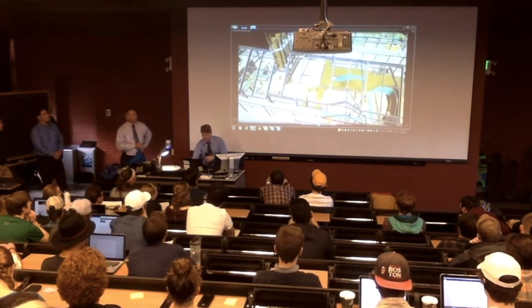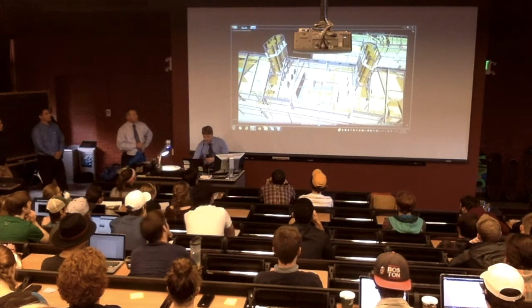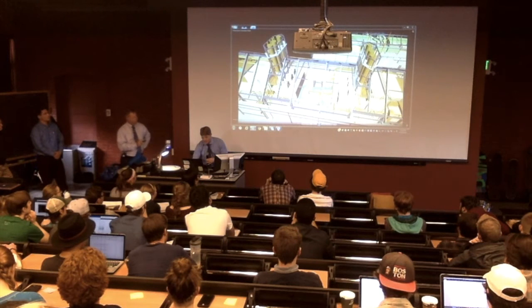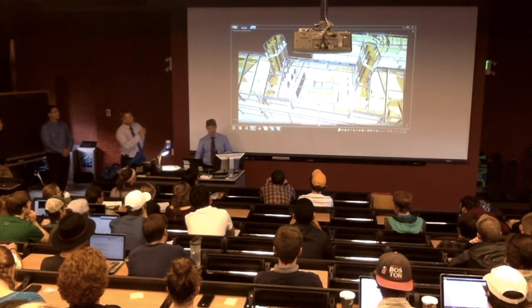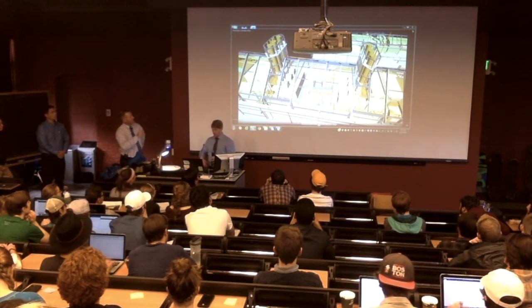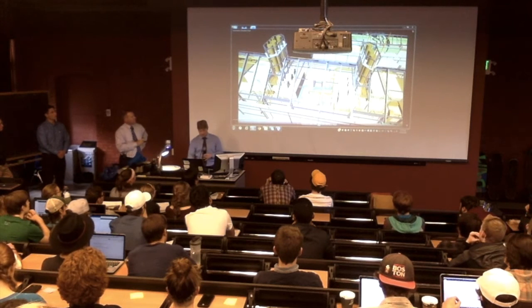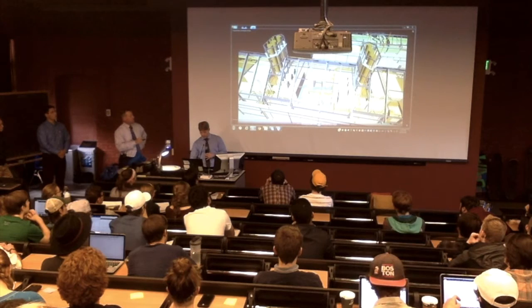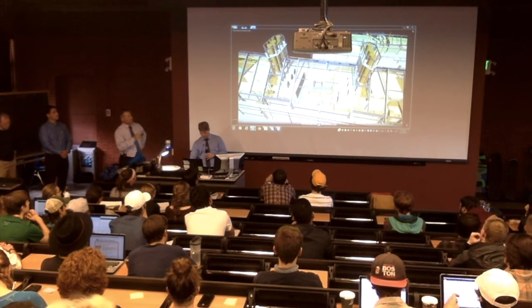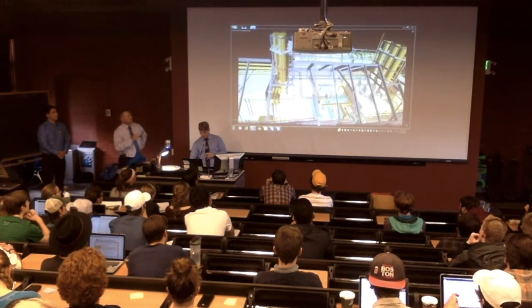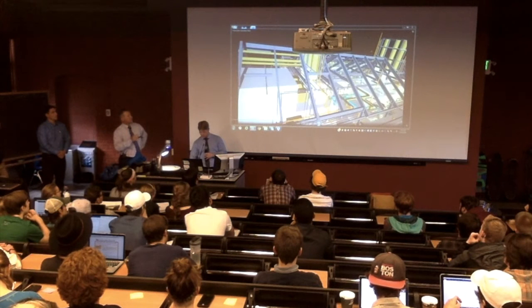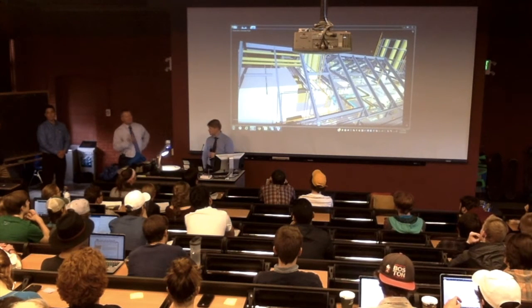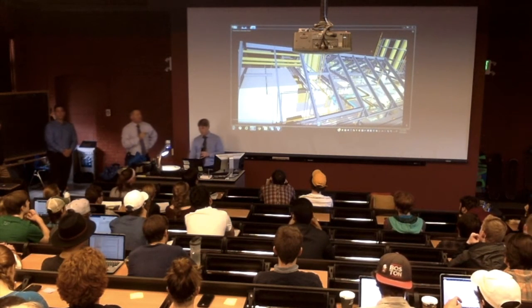So just flying over the top of the mechanical room here, like Al said, we've got our main air handling units with the big stacks off the top of them. So that's all your fume exhaust, your nasty stuff that you really want to get a high velocity out of the top of the building to keep it away from other air intakes and other potential contamination. So as an example, the organic teaching labs, the exhaust would go into the system and then be pushed up into the atmosphere.